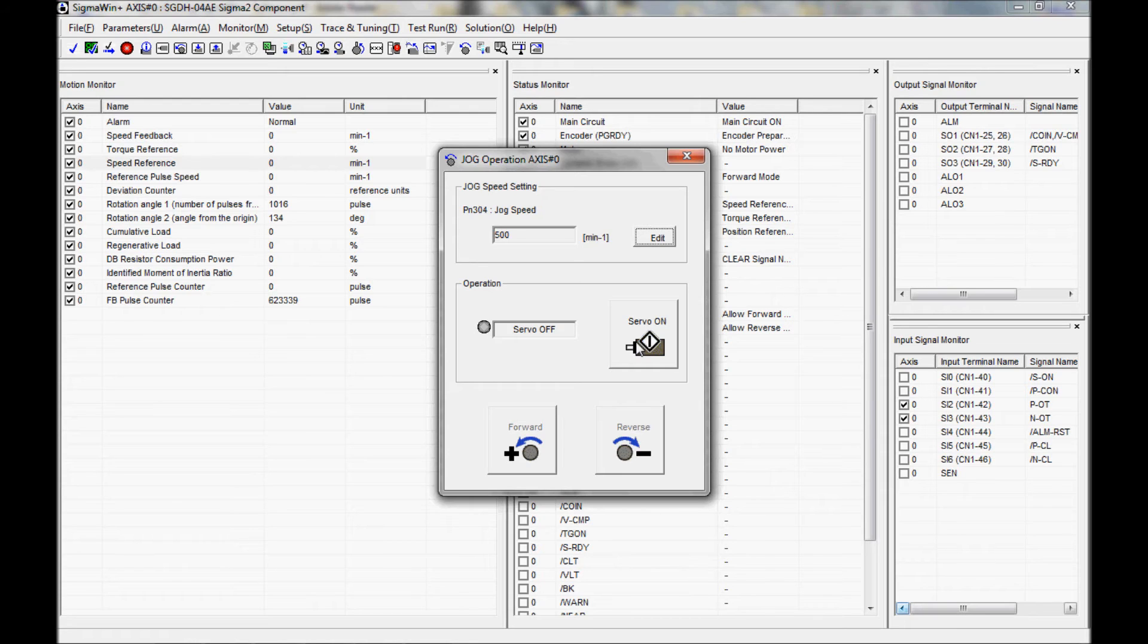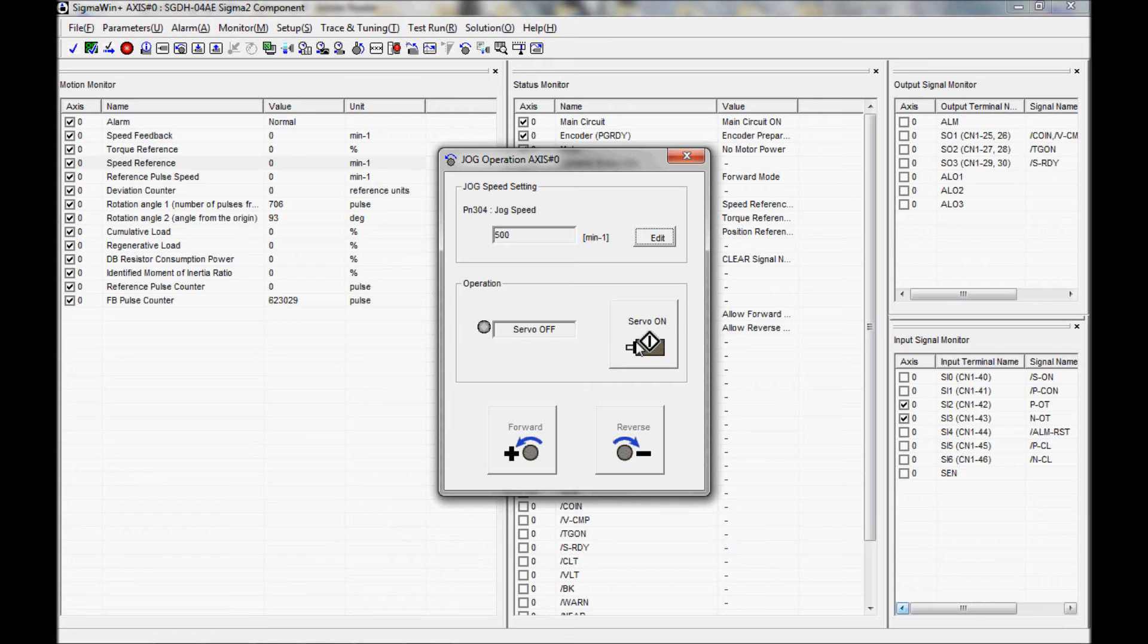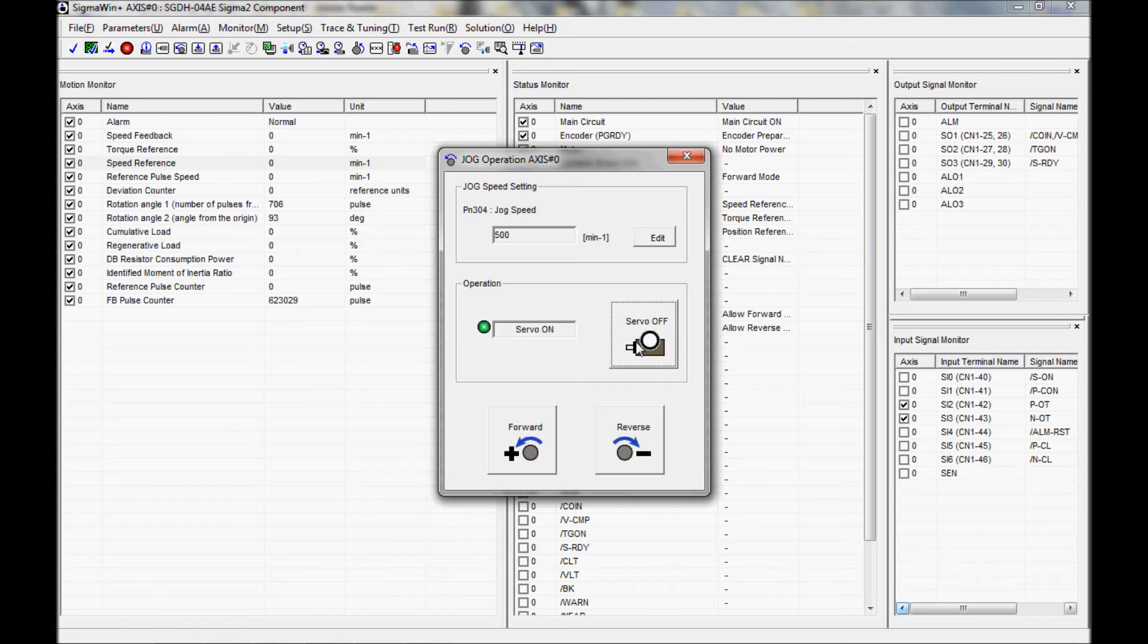Just down below in the operation section, I have a button that says servo on. What that does is it closes the main contactor inside the amplifier. It applies power to the motor. If you have a motor that does not have a brake on it, you can take and turn the shaft right now, just as I am doing. You can see the values for the feedback and the rotation angle are changing. That means there is no power applied to it right now, so it is not holding it in place. When I press this button, you might hear a click. What that does is it closes the contactor and applies power to the motor. I'm going to close the contactor now. And now I have power to the motor.